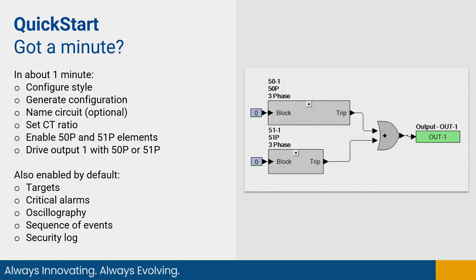After you make these hardware and firmware selections, the first thing you need to do is generate the configuration. What this does is it maps out the hardware based on the options you selected in the style configurator and creates circuits, breakers, inputs, outputs based on these selections. You can give the circuit a name and put in the CT ratio into the power system parameters.